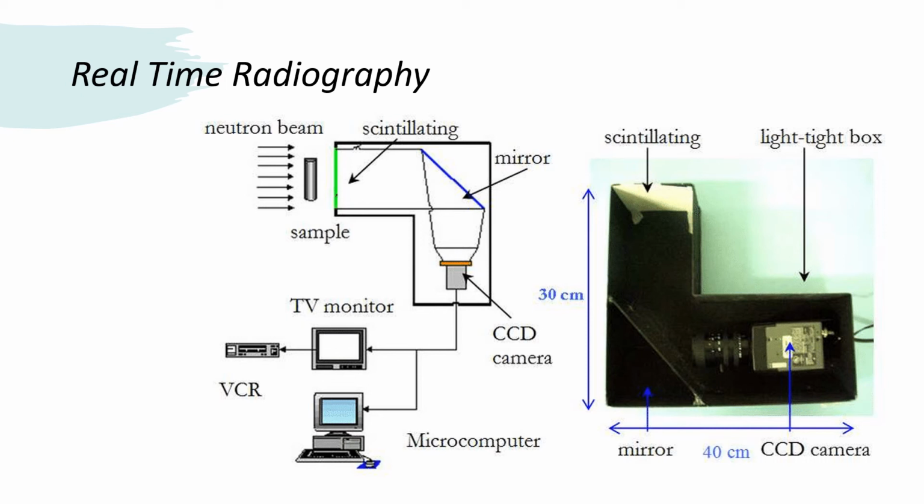presence or absence of certain components or materials, or the presence or absence of a bonding agent such as solder or brazing. ADR may also be used at very high speed for objects that can be scanned and interrogated by intensity statistics, pixel statistics, or similar window techniques for voids, inclusions or other anomalies with a good contrast against the surrounding material.